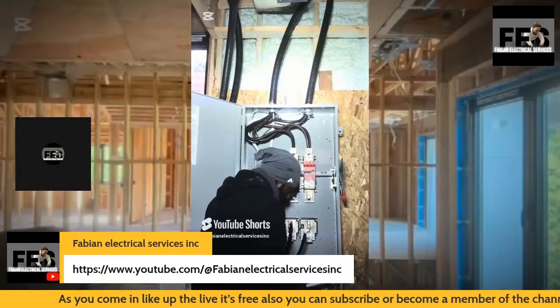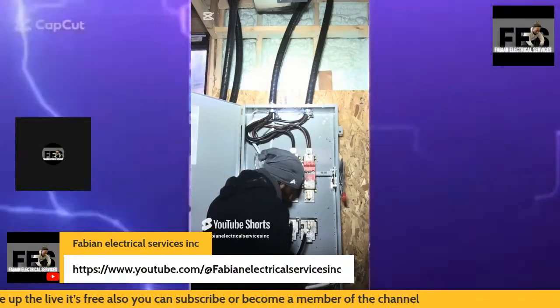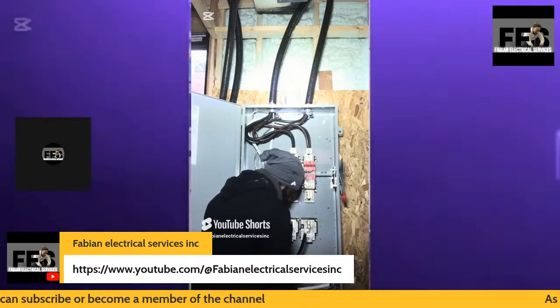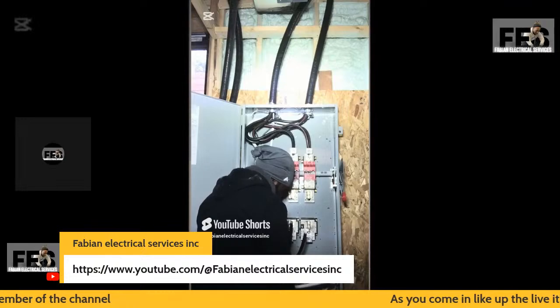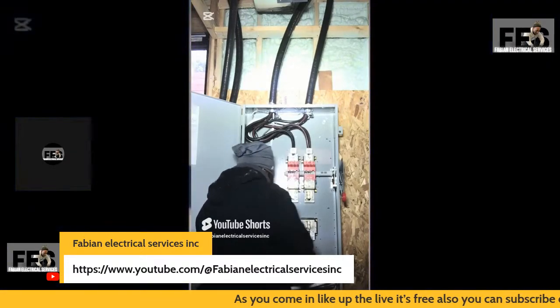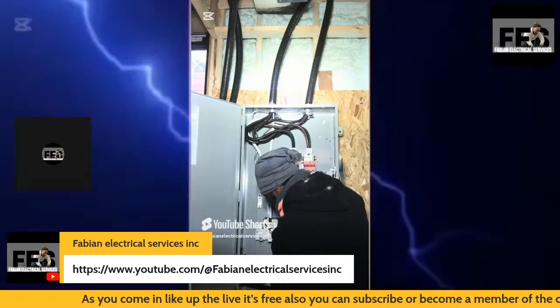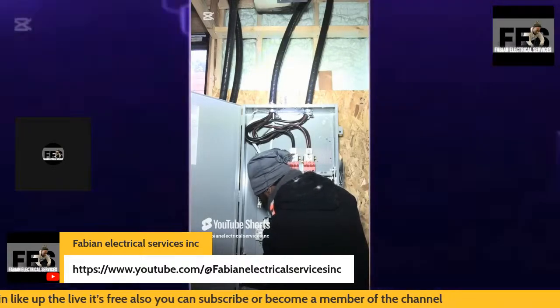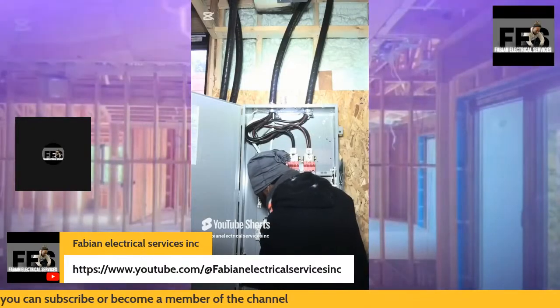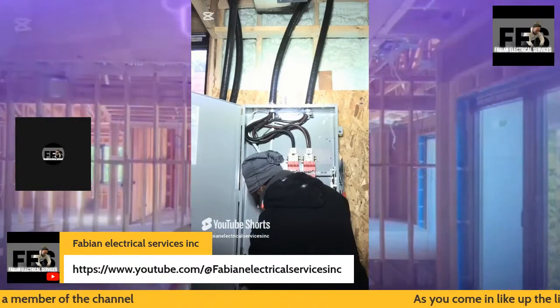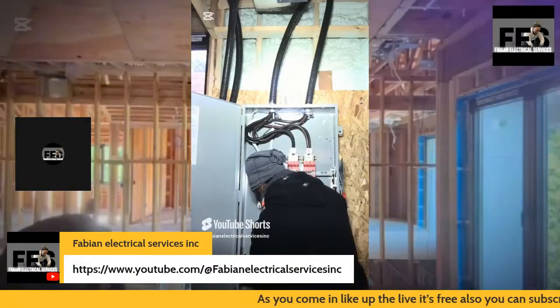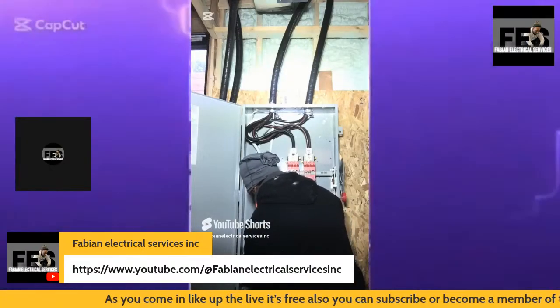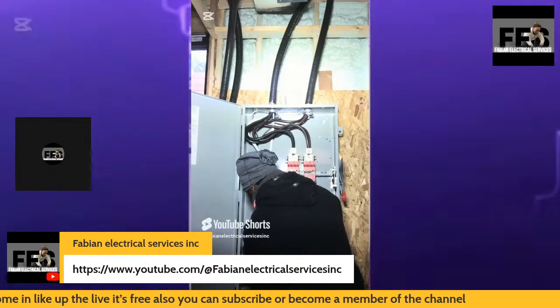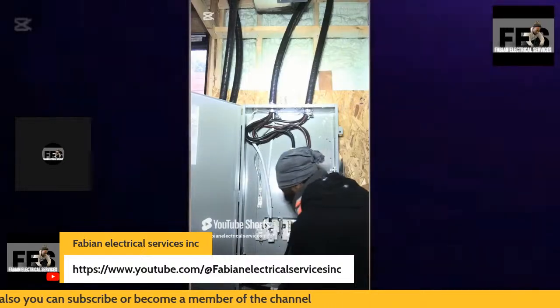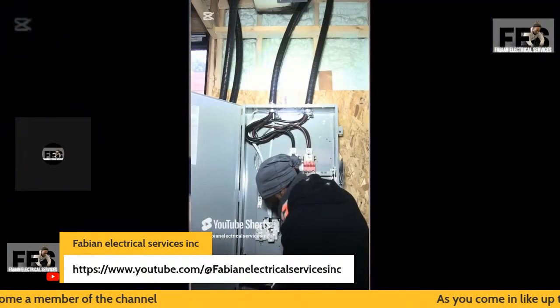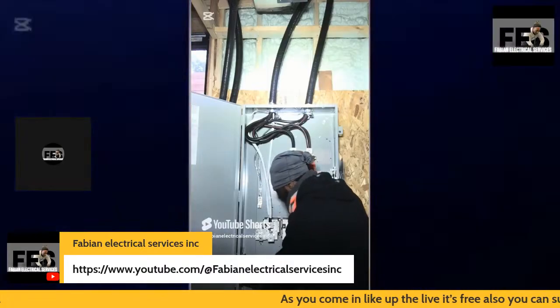Hello again, welcome back to the channel. I'm installing this tape because I have to identify my cable, which is the neutral I'm taping right now. A 400 amp disconnect fusible is here because the panel is located more than a certain number of feet from the meter base, and it's a code rule that if the panel is located more than a certain distance from the outdoor meter base, you need a means of disconnect. That's what's here, a 400 amp fusible disconnect, since the panel is located on the other side of the home.